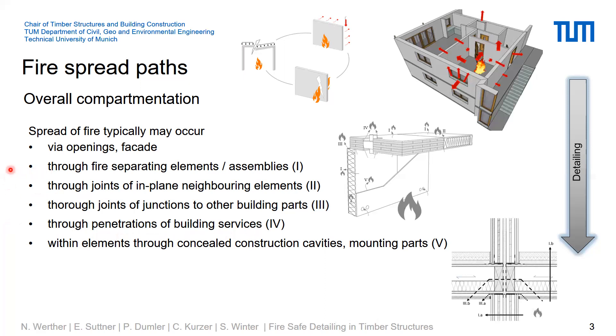Fire spread also occurs through the separating element itself when not designed properly, but also — and this is the main focus of today's presentation — via in-plane joints in neighboring elements and through joints to other building parts, like a wall-floor junction. The complexity of this topic becomes obvious when zooming in on such a detail, where you realize the joints, the gaps, the tolerances needed, and the potential risk, as well as which measures have to be taken to ensure fire safety.